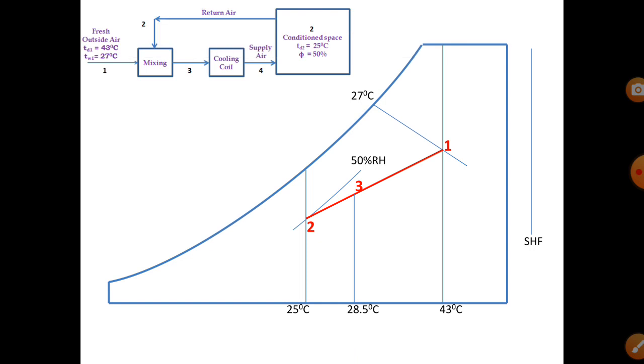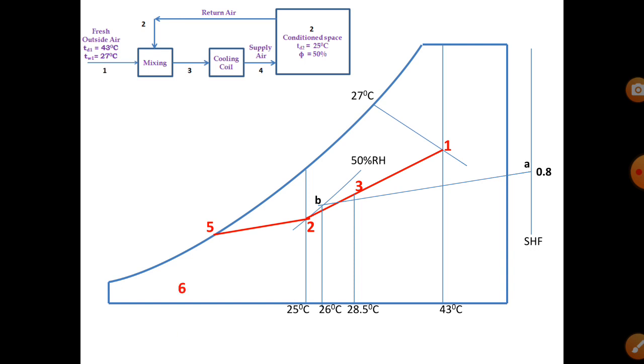On the SHF scale, mark point A at 0.8. Point B is the alignment circle at 26°C DBT and 50% RH. Join A and B, then draw a parallel line through point 2 — that is the line 2 to 5, which is the RSHF line extending to the saturation curve. Then draw one line through point 3 to the ADP temperature, which is the cooling coil temperature.